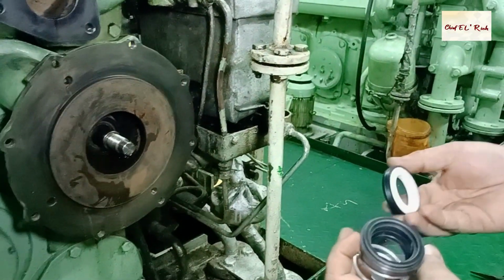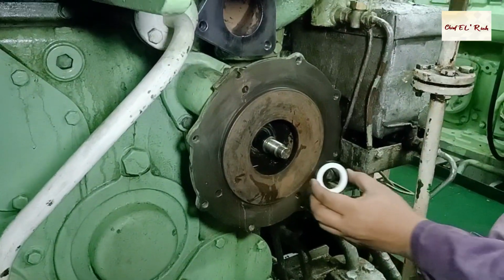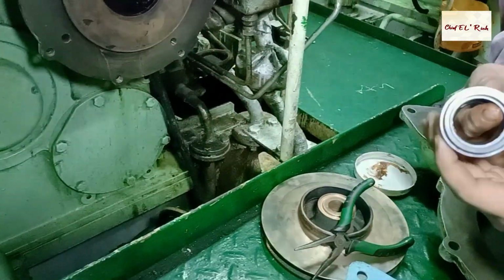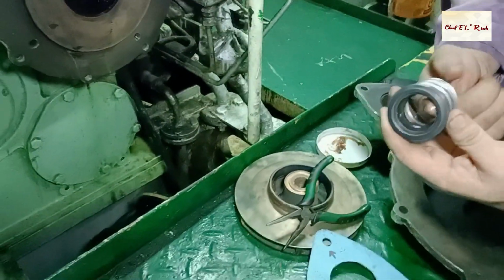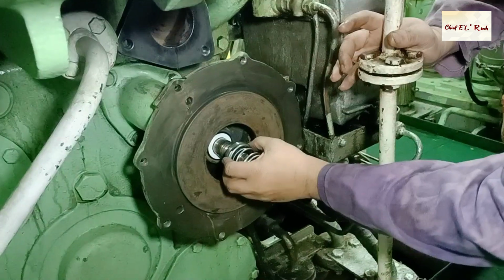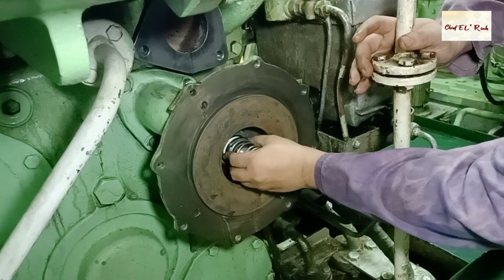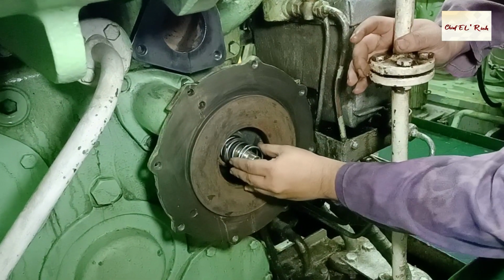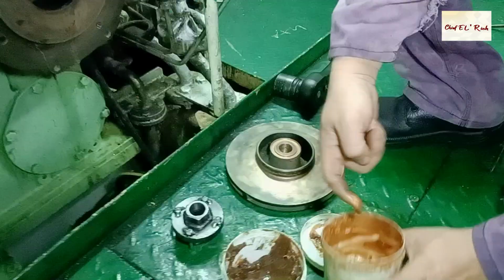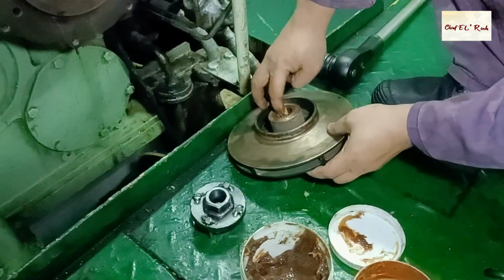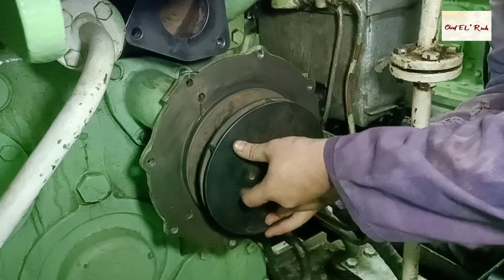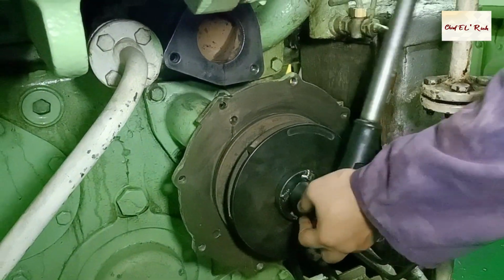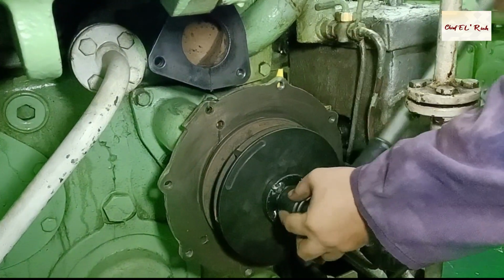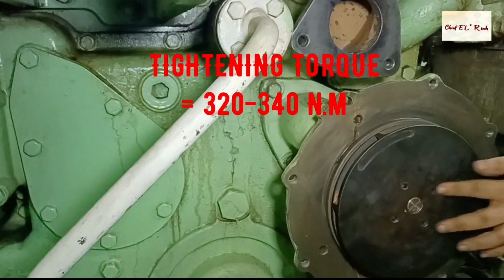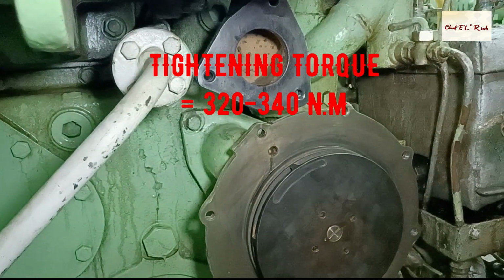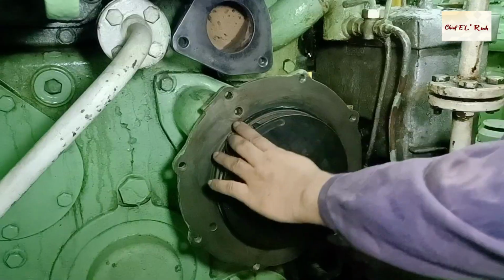Clean the entire surface and install the mechanical seal. Use grease when inserting the mechanical seal onto the shaft surface so that it will slide smoothly. Do it slowly and be careful not to break the sealing carbon of the mechanical seal. Once the mechanical seal is in place, install the impeller. Put anti-seizing compound and tighten in counterclockwise direction until it is flattened on the last surface of the thread. The tightening torque of the impeller is 320 to 340 Nm.